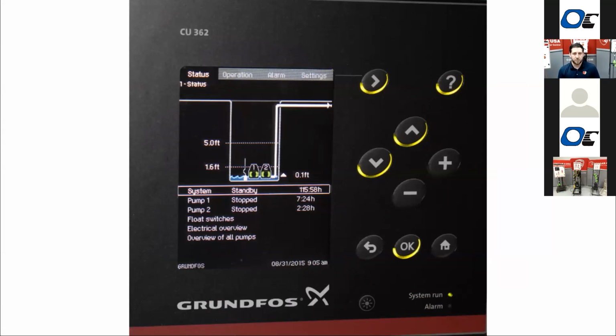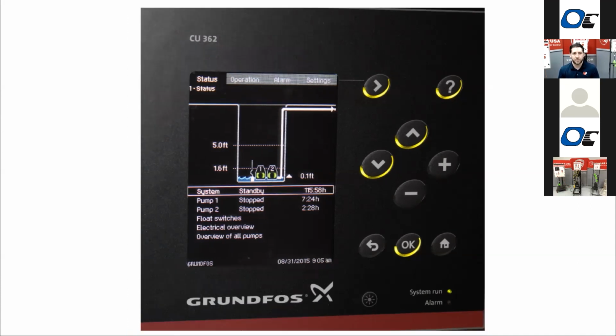And then the step up from there is what we consider dedicated controls. Basically, it is still a PLC type controller, but it is designed even more specifically for that application. This is hardware and software that Grundfos manufactures, a CU362 controller. If anybody's familiar with the booster systems from Grundfos, it's the same hardware, just with a different program on there. They've gone deep into the sump station design and can do some really cool things in there. Like, you can do volume calculations, flow calculations, control up to, I think, about 5 or 6 pumps, things like that. So it's a very deep dive into the controls features for a sump station if we move to a dedicated controller like the CU362 there.